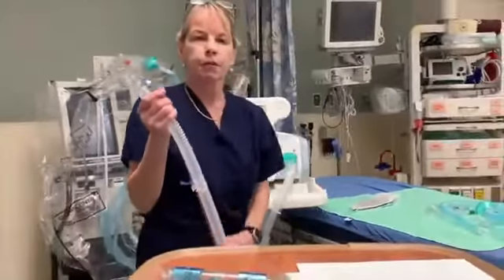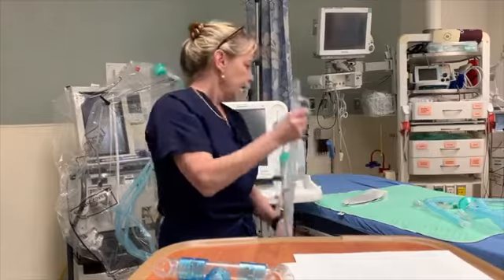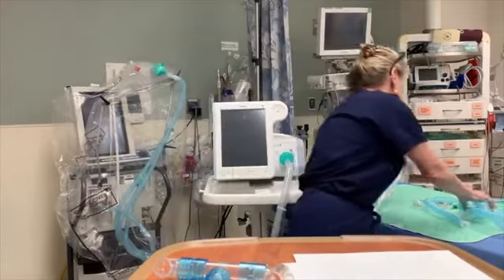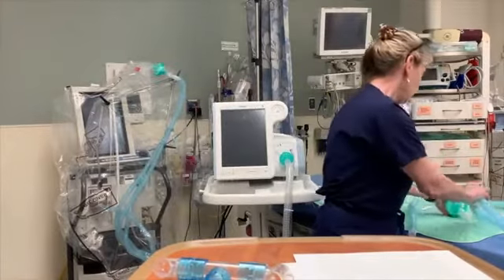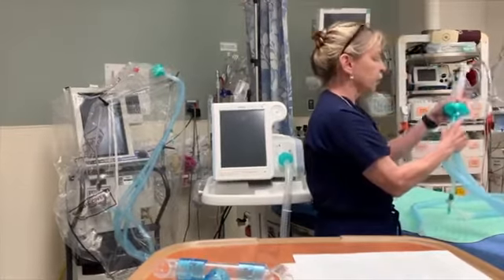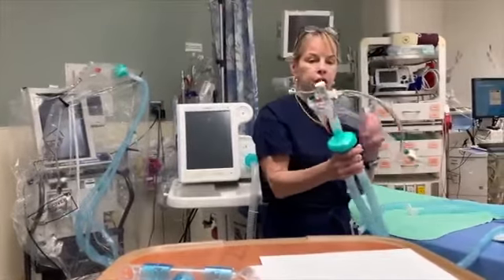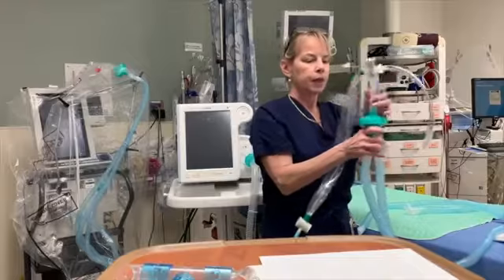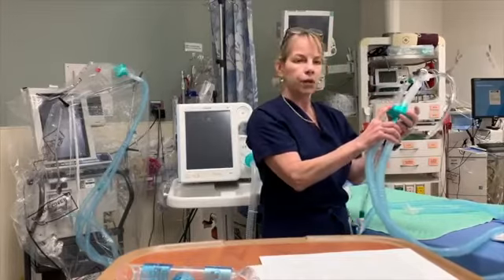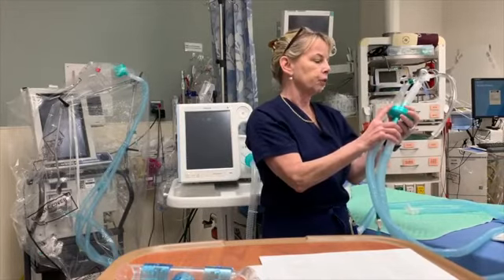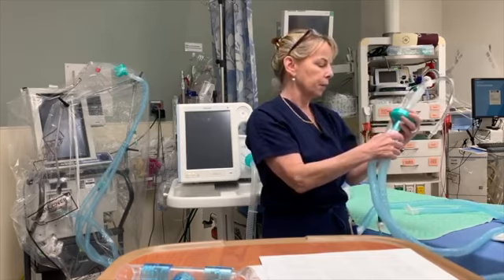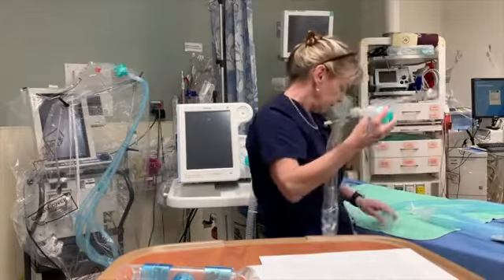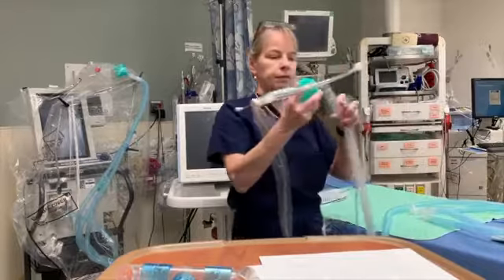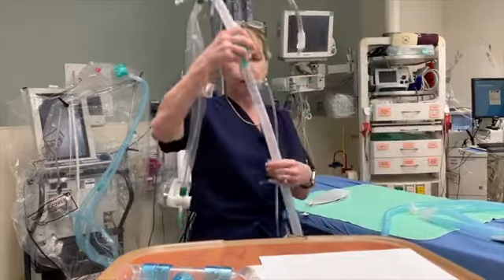So the tubing you use is the same tubing that you would use for Bi-pap, just one tube, and on the end of it, you have to stick the device that you would normally use hooked up to your ventilator. So this is our tubing we have here that we use for patients who are intubated. Here's our ET tube. Here's a 2-way infection valve that filters viruses and bacteria. And so I'm just going to take it off the ET tubing, and I'm going to put this end on the end of the tubing that we are going to be using, which is our Bi-pap tubing.